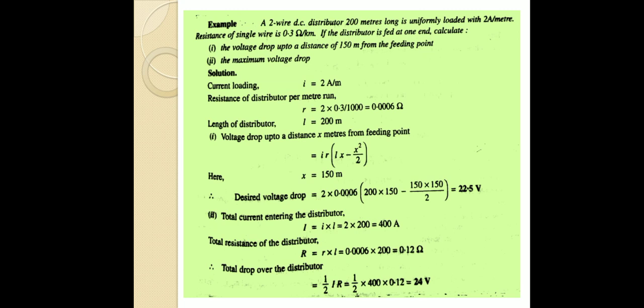For number 1, the voltage drop up to a distance of x meters from the feeding point uses the formula: voltage drop equals IR into (Lx minus x squared by 2). Here x equals 150 meters. Substituting: 2 into 0.0006 into (200 into 150 minus 150 squared by 2), which gives 22.5 volts.